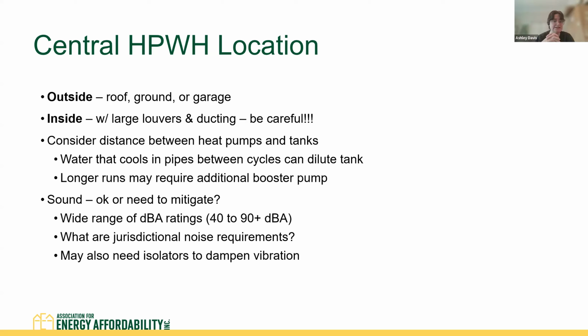You may also need to think about the distance between your heat pumps and your tanks, right? It's a lot of piping running between them, and water cools down in the piping. It can dilute the tank if you have large volumes of water sitting in the pipes, cooling down when there are periods when the heat pumps aren't on. Sometimes you're even going to need an additional booster pump or tank between your heat pump units and your primary storage tanks if they're too far apart.